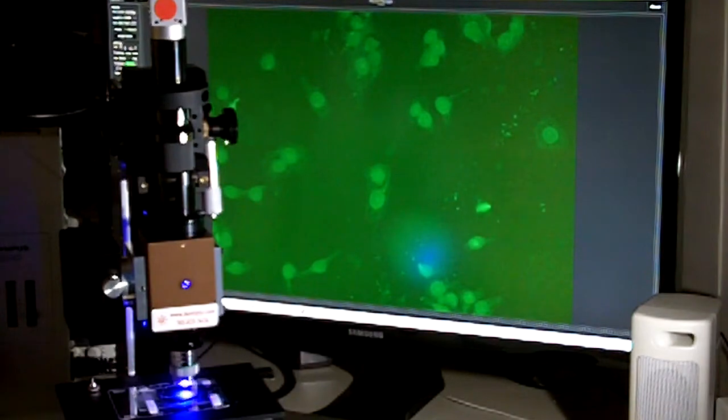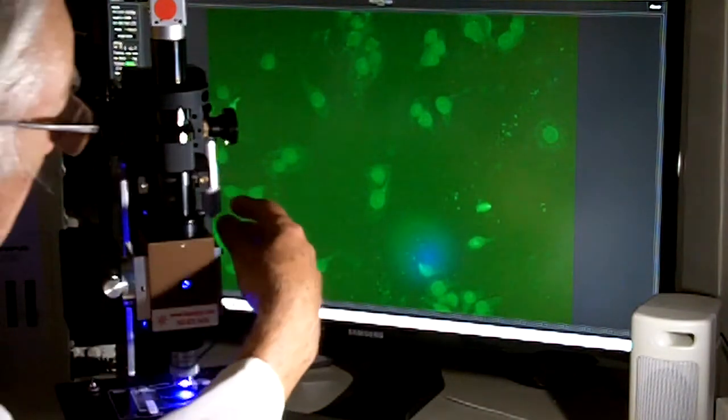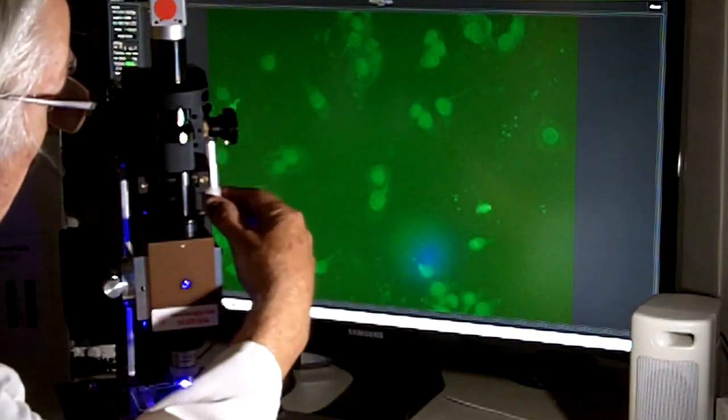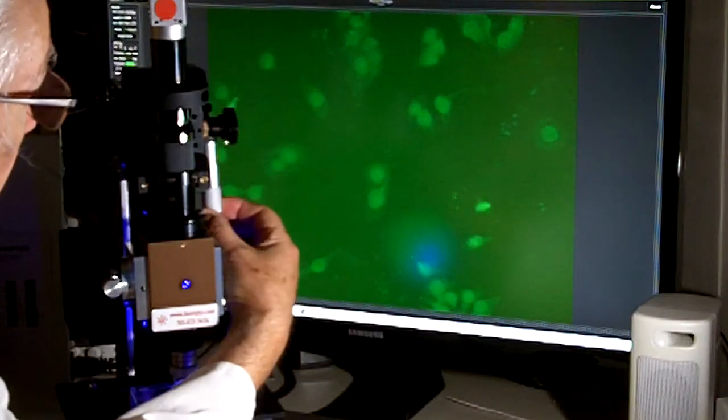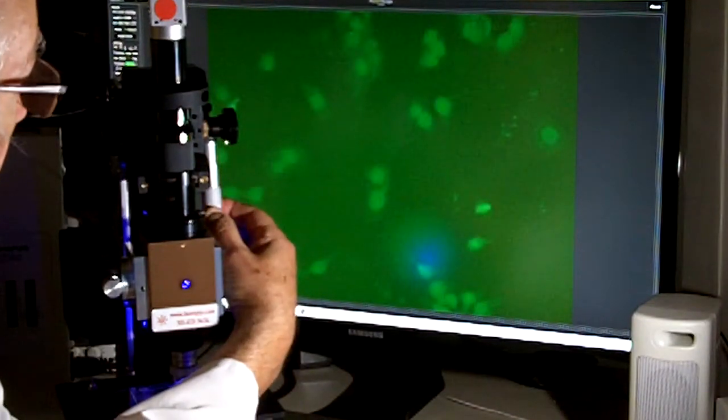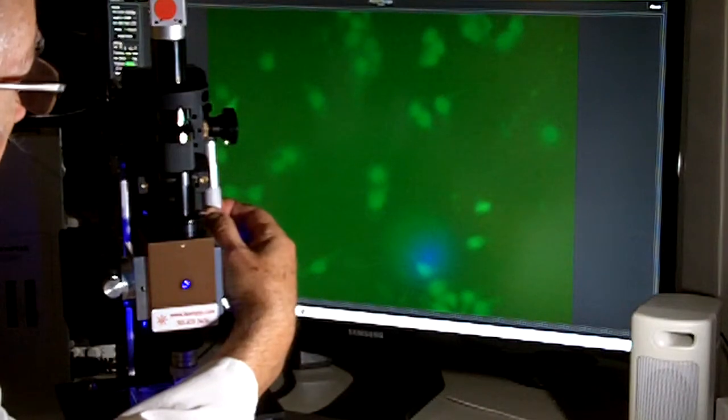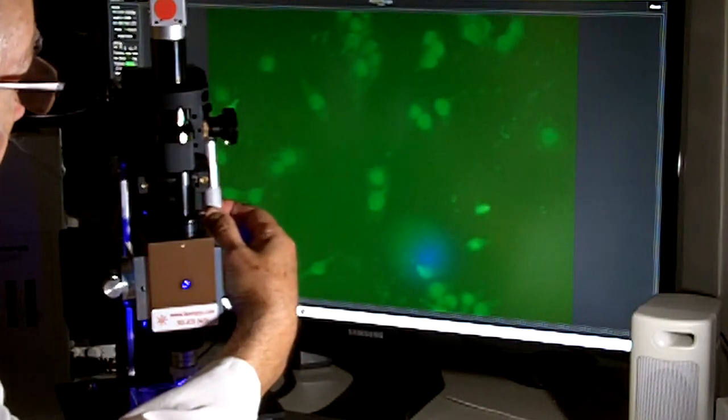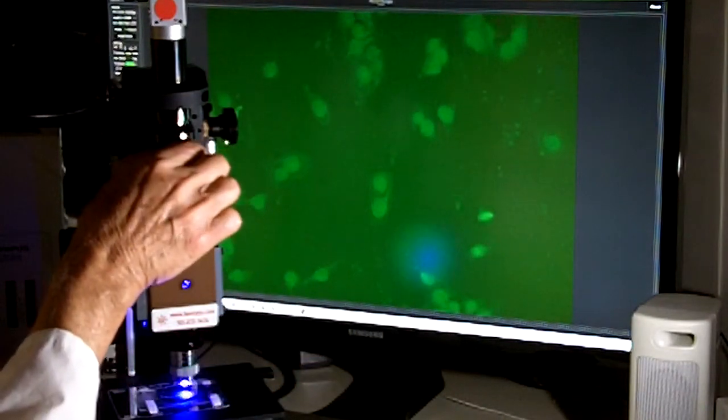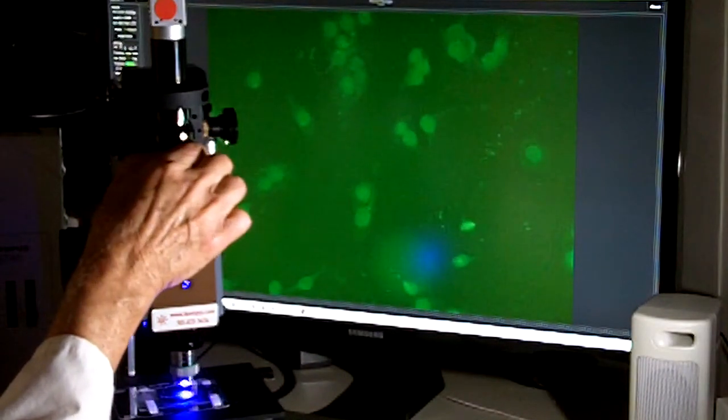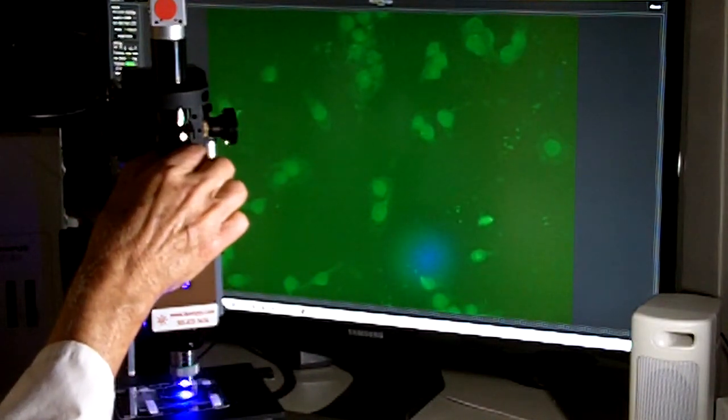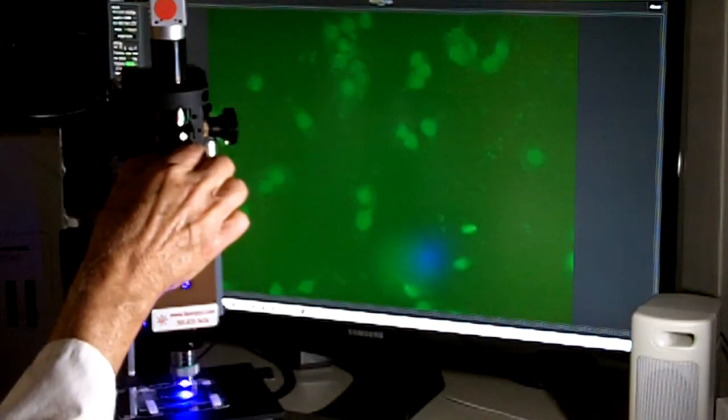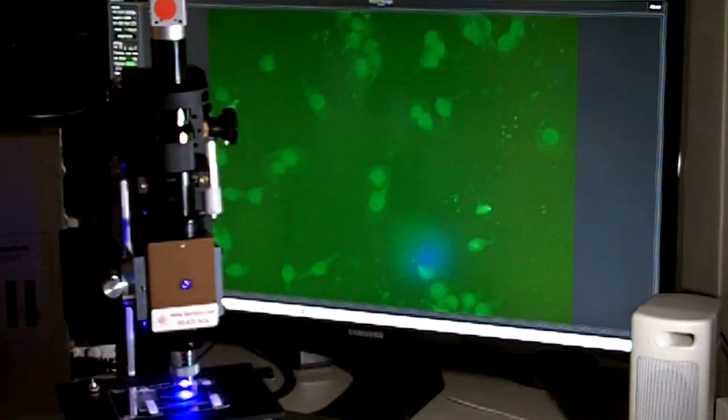Now, to do focusing, we can use the fine focus. It's a micrometer drive here on the right. This allows you to fine focus whatever you're focusing on. But once you're in the ballpark, you can also use the integrated focusing mechanism that's part of the KC microscope.